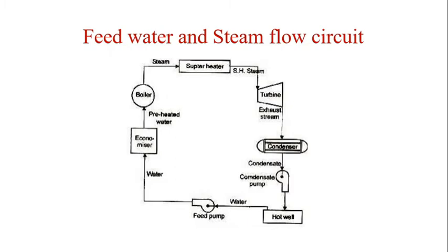In the water and steam circuit, condensate leaving the condenser is first heated in a closed feed water heater through extracted steam from the lowest pressure extraction point of the turbine. It then passes through a deaerator and a few more water heaters before going into the boiler through the economizer. In the boiler drum and tubes, water circulates due to the difference between the density of water in the lower temperature and the higher temperature sections of the boiler. Wet steam from the drum is further heated up in the superheater before being supplied to the prime mover.